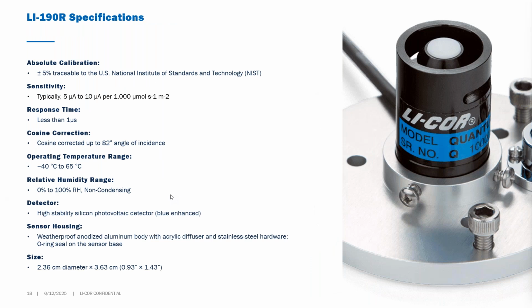So a little bit more about the sensor itself. They come factory calibrated, plus minus 5% traceable to NIST. Sensitivity piece, all these sensors, their output is a pretty low current output, typically from 5 microamp to 10 microamp per 1000 micromole per second per meter square. But I'll touch on why it's critical and why I'm speaking of that when it comes to calibrating sensors. Super fast response time, cosine corrected to 82 degree, as I mentioned earlier, and then a good range. You'll notice on the high range between the data logger and the sensor, there is a bit of a difference. So the data logger is rated up to 70C and the sensor itself at 65. So more often than not, both will be in the same environment, so I would just look at 65 degrees as the high end.